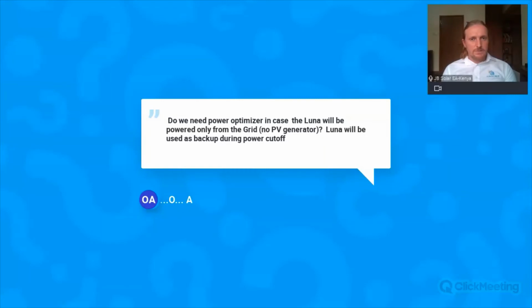Do we need a power optimizer in case the Luna will be powered only from the grid, with no PV generation, used as backup during power cutoff? No, you don't need an optimizer. An optimizer attaches to the back of a solar panel, so if there's no solar, there's no optimizers. Now, if your Luna will be powered only from the grid with no PV generator, that can work, whether single phase or 3-phase.